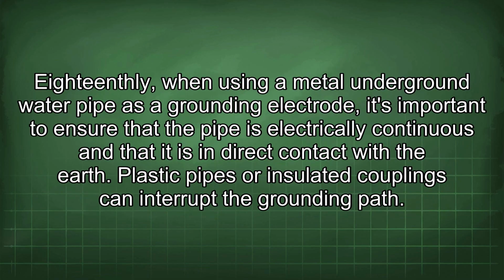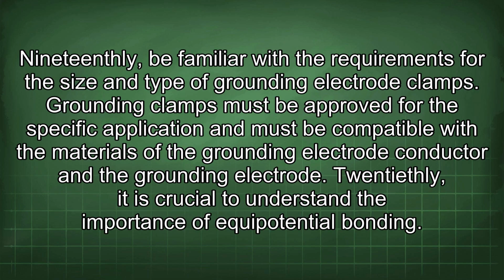18thly, when using a metal underground water pipe as a grounding electrode, it's important to ensure that the pipe is electrically continuous and that it is in direct contact with the earth. Plastic pipes or insulated couplings can interrupt the grounding path. 19thly, be familiar with the requirements for the size and type of grounding electrode clamps. Grounding clamps must be approved for the specific application and must be compatible with the materials of the grounding electrode conductor and the grounding electrode.